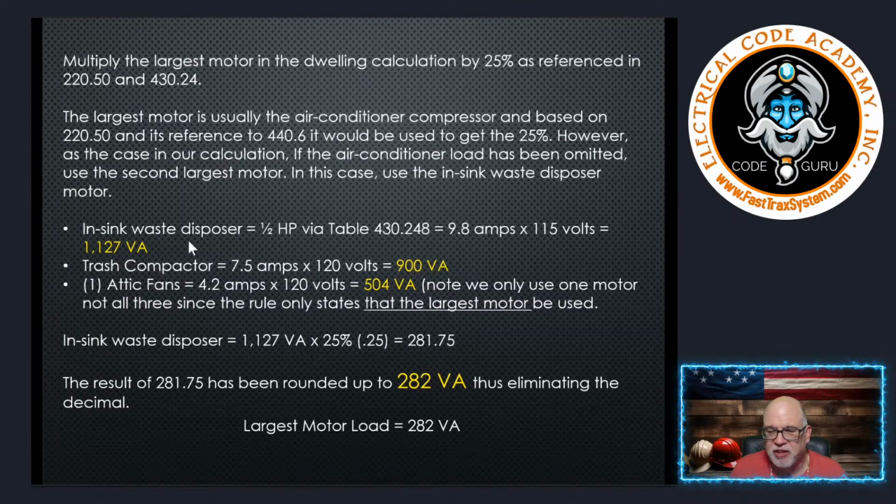And again, people say, well, why did we not use the AC? Because that is the largest motor. Because we discounted that entire load when we did AC versus heat. So it's gone. That's why we're hunting for the next largest motor. And that's what we got, the InSinkErator waste disposal. That makes sense, I hope. And if you don't believe me, you have to have a leap of faith here. That is exactly how it works. I've been teaching this for 38 years. That is how it works, okay?